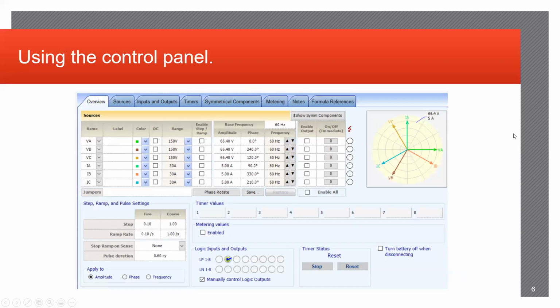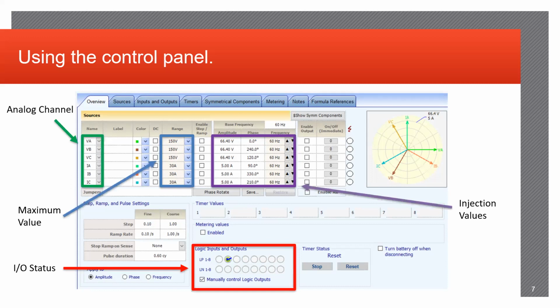The control panel in the 6150 software is also extremely useful for not just your test plans, but any random voltage or current injections that you may be doing for other test purposes, such as functionals, metering purposes externally, as well as automation testing, identifying that if the relay is picking up currents and voltages and sending them to the client's dispatch or HMI screens as well, that you can use this to directly set up your current and voltage leads, set up your amplitude and phases, et cetera, and we'll go into that detail right now.